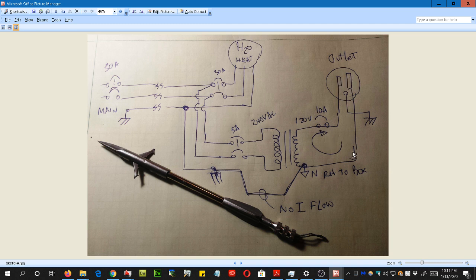So we run it up to the outlet. There's the neutral coming over. I don't ever like having a secondary floating, so you got to reference it. A lot of times I'll do the center tap and reference that. I drew it on the bottom here so it wouldn't get too confusing, and then I'm going to rehook that and reference it to ground over here. The current is not going to flow through here. The current wants to get back to where it came from, so it's going to flow in this loop here. So I've now satisfied by getting him 110 in his outlet and not have a ground current. So no current here will flow. If you have a current here, you're doing something wrong. And that's the one I posted earlier. Let's see where we're at now.